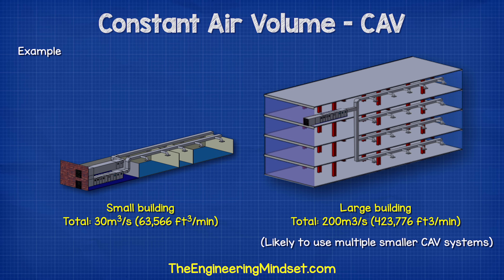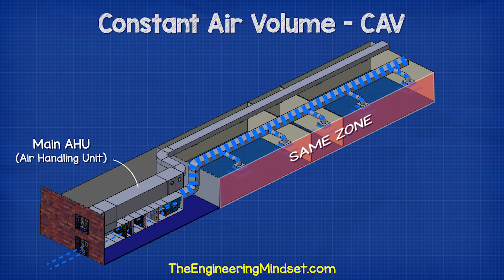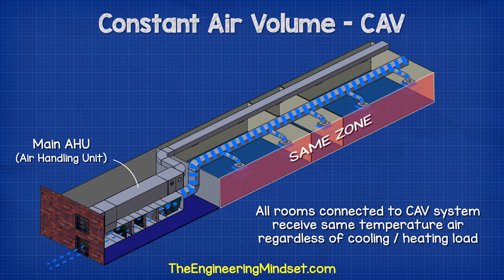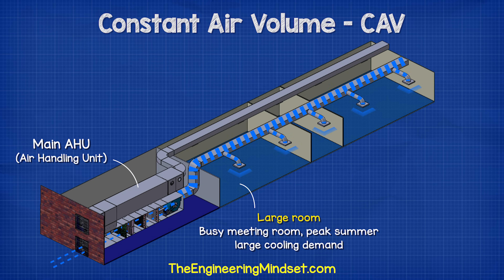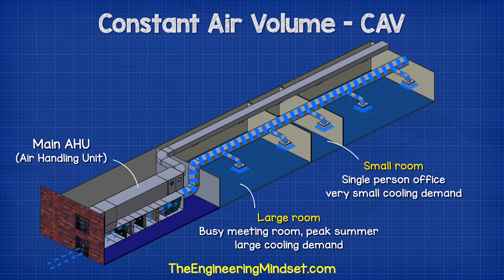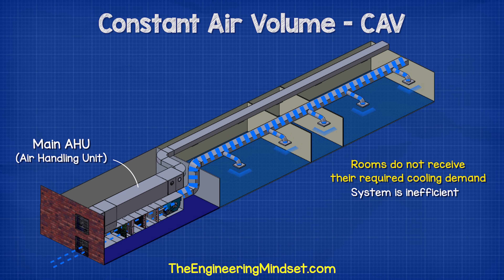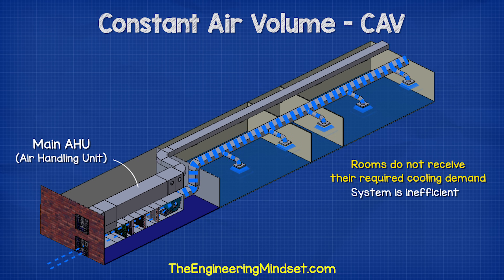One of the main problems with the CAV system is that everything connected to the AHU and the supply duct is classed as one zone. That means all the rooms connected to it will receive the same temperature air regardless of their cooling load. For example, this could be a busy meeting room in the middle of summer with a very large cooling demand from solar thermal heat gain, but this room will receive the same temperature air as a tiny office for one person. That's going to be very uncomfortable. This means the rooms are not receiving their required cooling demand, so the system is very inefficient because we're generating a lot of cooling which is simply being wasted.